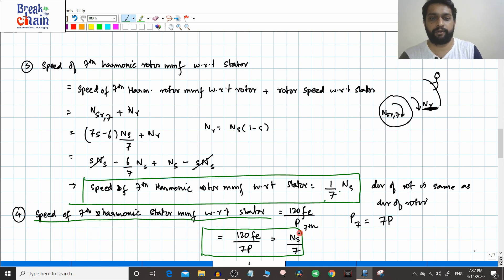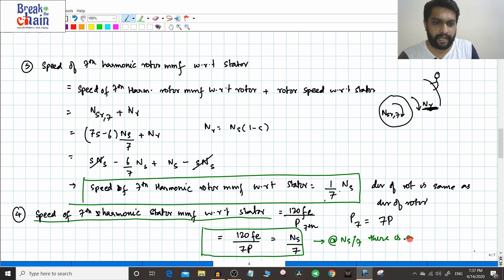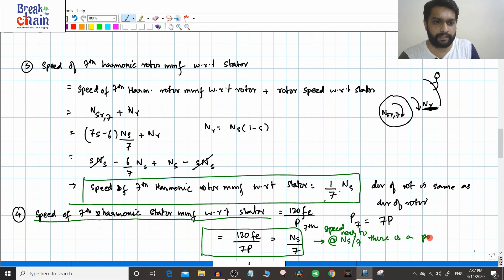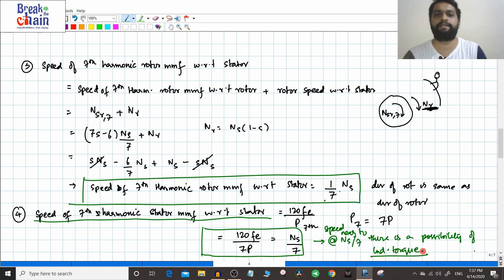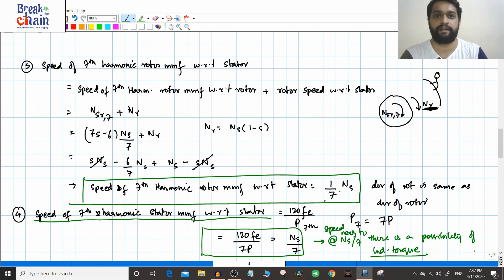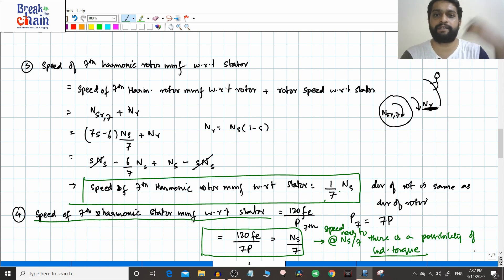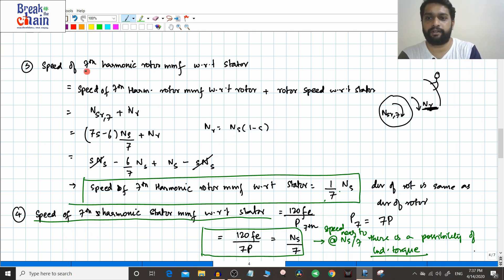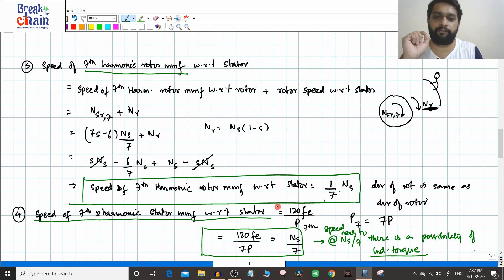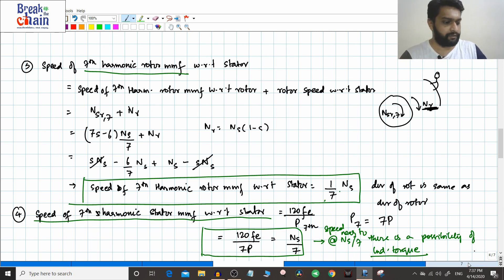Because both the 7th harmonic rotor MMF and the 7th harmonic stator MMF are stationary with respect to each other at ns/7, there is a possibility of induction torques at speeds near ns/7. That is how the crawling phenomenon happens — just as for the fundamental torque the fundamental rotor MMF and stator MMF must be stationary with respect to each other, here the harmonic MMFs are also stationary with respect to each other, enabling torque production.